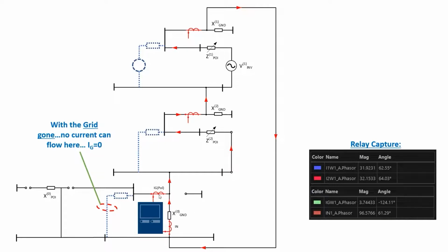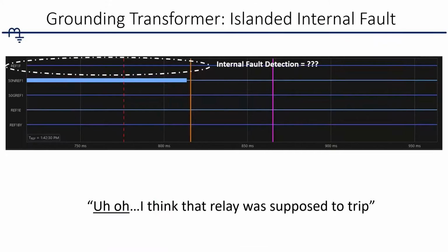And the exact reason for that is the grid is no longer present. So if you were to put this shunt here, you would get a current flow through this portion of the branch, which we do not have because it's grid isolated. So you would expect to only see IN and not IG, which presents a problem. What do we do now? We said that we're doing an angle comparison. So how does that work if you don't have an angle to compare to?